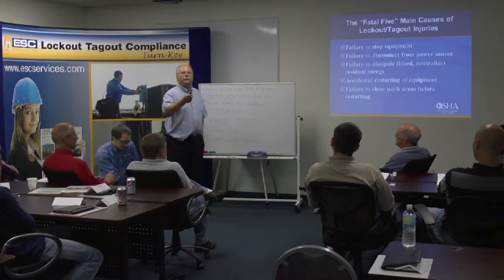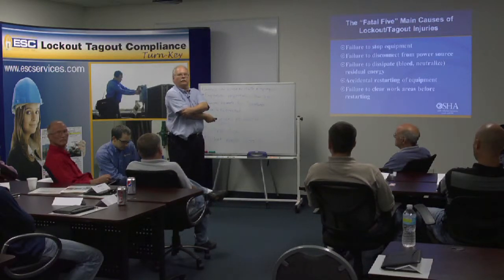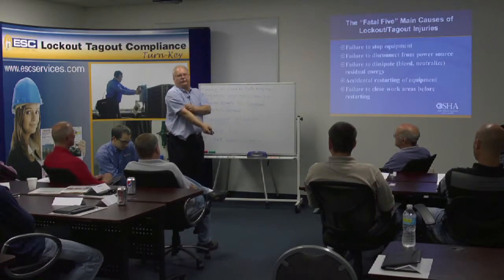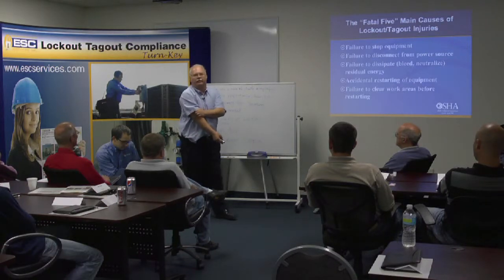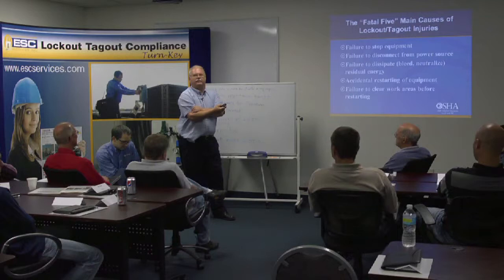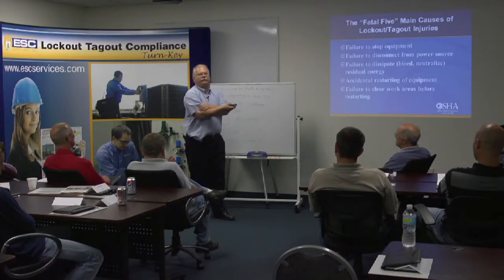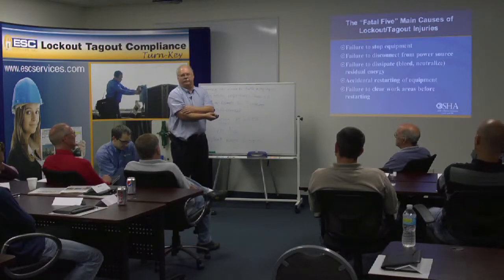Question: that wiring system technically has two sources of power because of two switches — does it need a procedure? Under OSHA, for lighting systems, they still have that 1989 NFPA interpretation. The new 70E, as of 2004, 2009, and 2012, removed that. You could disconnect it by going to the disconnect at the panel, which the electrician did not do. Since there are two sources in the room, he would have to identify both and have a procedure, or go back to the box for the lockout procedure.